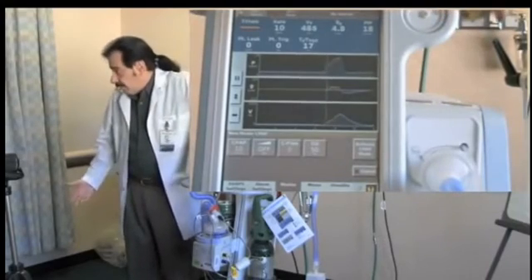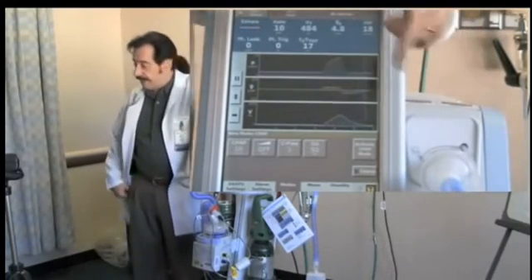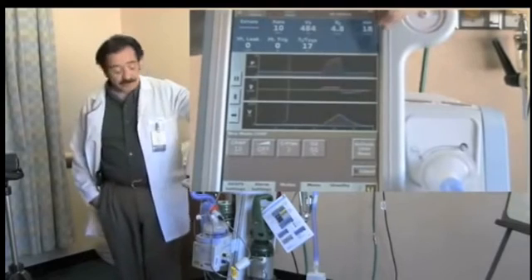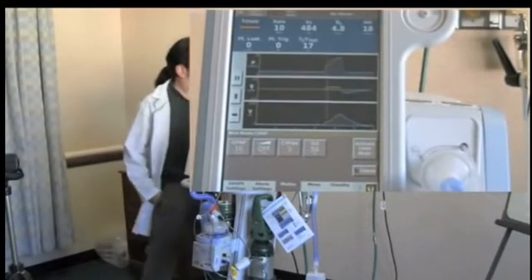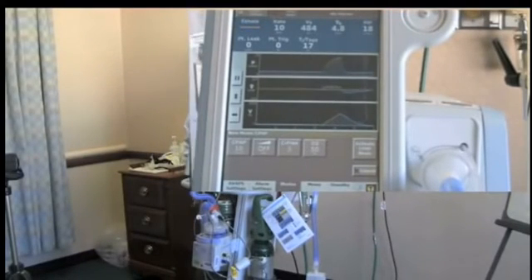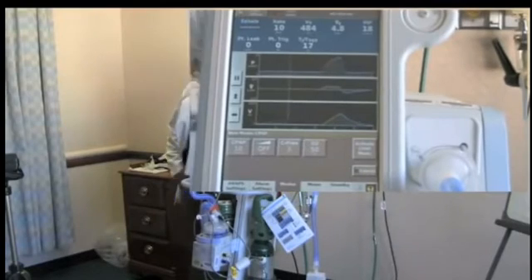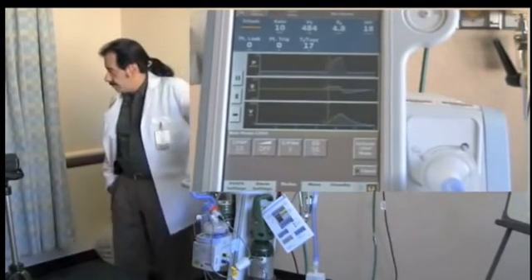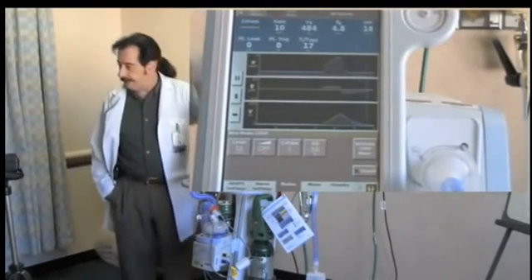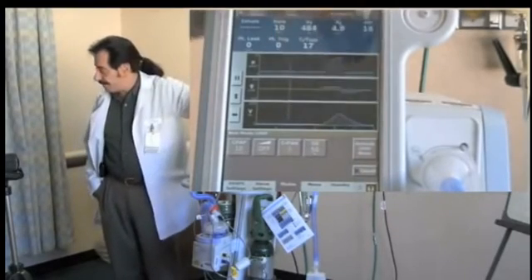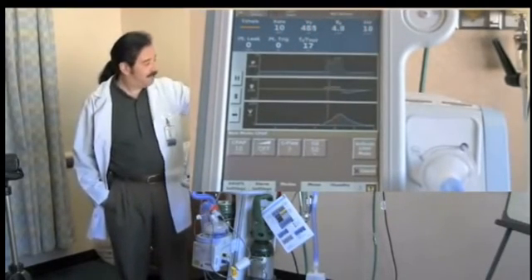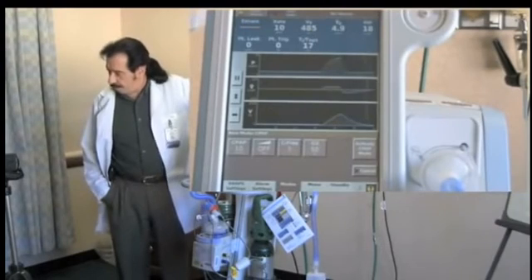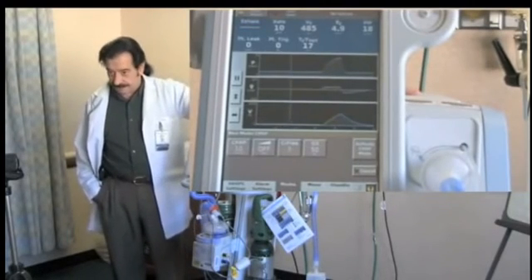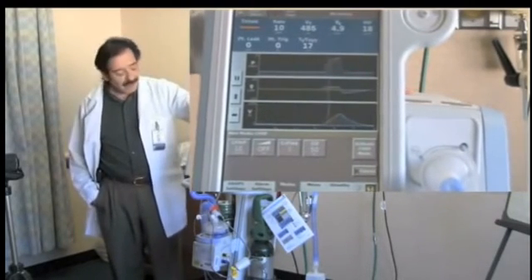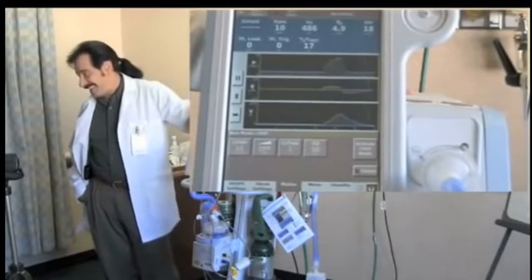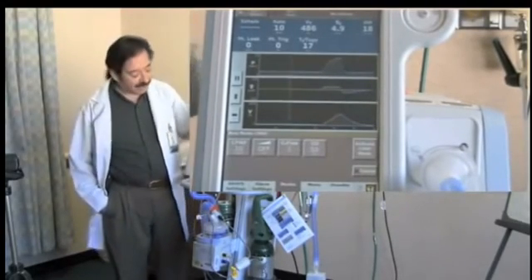Either just leave it on all the time, or at least when you're doing vent checks, validate your FiO2. Make sure that's what you're getting. Because I could have this hooked up to an airflow meter, 50 psi. It knows there's 50 psi going in, but it doesn't know what it is. So if it was air, I could say give me 50%. It's giving me 50% of that pressure, or that flow from the wall source, and 50% from the internal, I call it the blower. But it's not guaranteed that that's a true oxygen concentration.